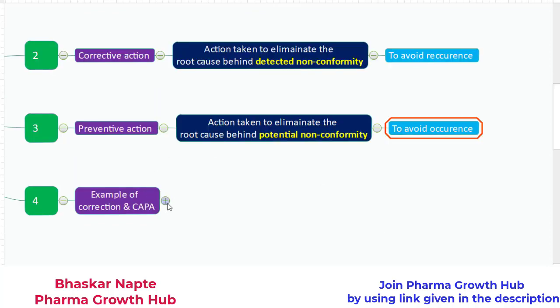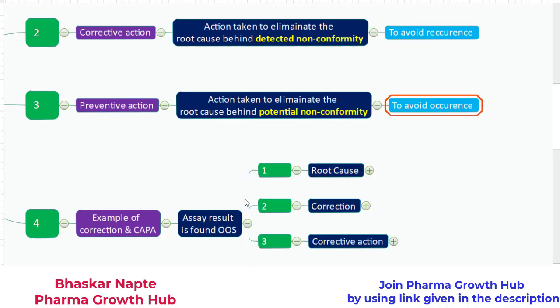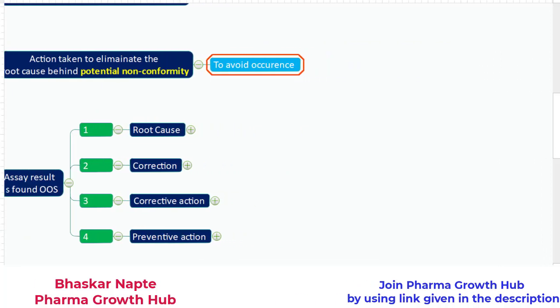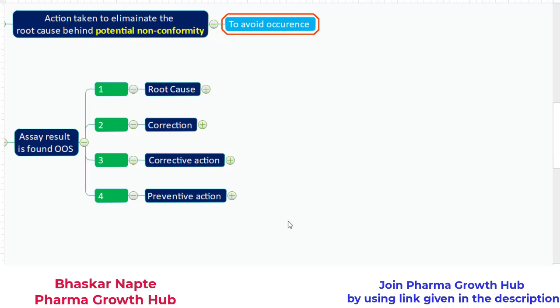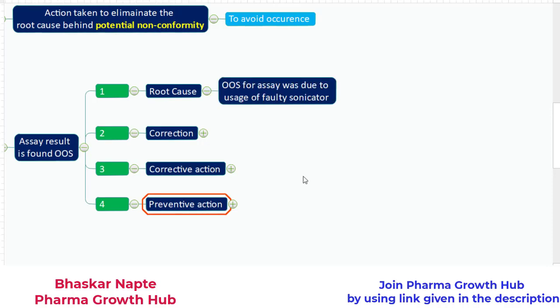Now let us talk about an example. I have taken an example of an OOS result where the assay result is found to be out of specification. As part of investigation, you are going to identify the root cause, and once identified, you define the correction, corrective action, and preventive action. According to the investigation, the OOS for assay was due to usage of a faulty sonicator. The sonicator is your extraction tool — it extracts the sample from the sample matrix. If the sonicator is faulty, there can be poor extraction, which further leads to a poor assay result. So the root cause is: usage of a faulty sonicator.